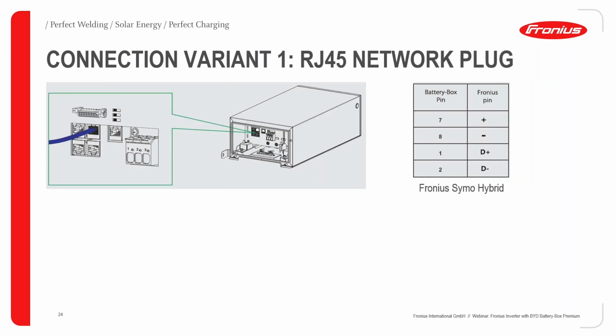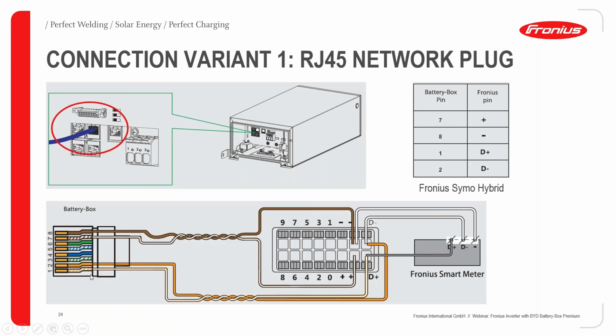We'll go through the two variants here. First, the RJ45 network-type connection. At this end, you'd use this connection block here - pins 1 and 2, which are your MODBUS, D+ and D-, and then pins 7 and 8, which are your negative and positive terminals. The negative is for your ground, and the positive, like the B-Box HV versions, is used to detect that the battery is connected.